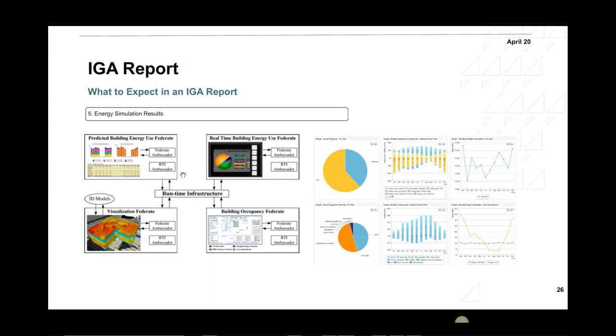And then I would put my energy conservation measures into the software. Let's say I'm changing the chiller. In the baseline model I had an air-cooled chiller with an efficiency of, let's say, 1.7 kilowatt per ton, and I'm putting in a new air-cooled chiller, maybe with a 46 degree C efficiency of 1.4 kilowatt per ton, or 1.3, whatever it is. I put that input in and rerun the model to check the effect on energy consumption. If I'm changing the lighting, I have a compound effect: I'm reducing the energy consumption from the electrical part of the lighting system, and I'm also decreasing the loads on the air conditioning equipment. So the energy modeling software will give me that compound effect, both the electrical reduction from the lighting system and the reduction on the air conditioning system. So energy modeling is a very powerful tool that gives you better accuracy compared to, let's say, just doing an Excel sheet calculation.